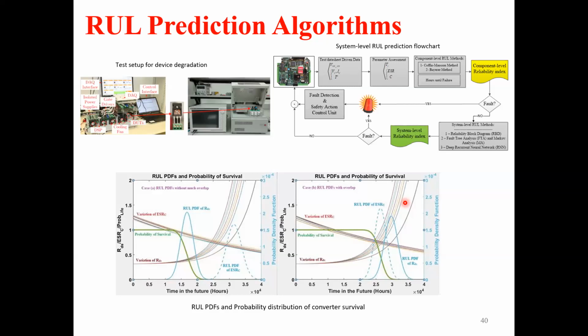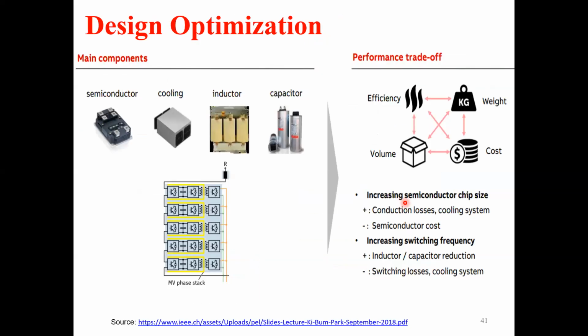So for example, with medium frequency transformer, I think we may be able to achieve almost 20 years of life. With high frequency, considering there will be more stress on the devices, maybe we can look at somewhere around 15 years of life. So for such designs, we'll be good with solid state transformers already. And then again, these are some research areas which are being followed.